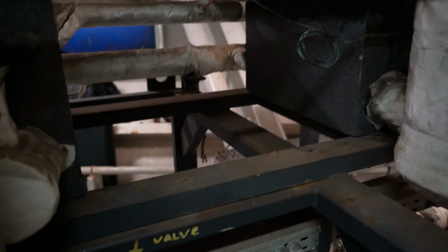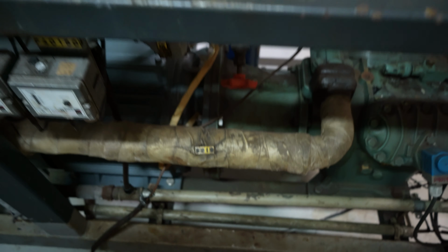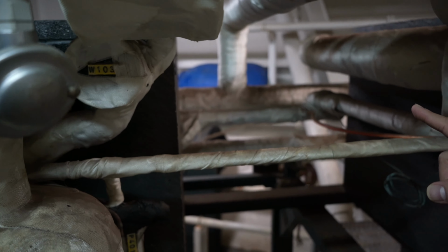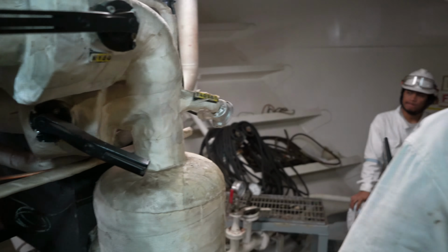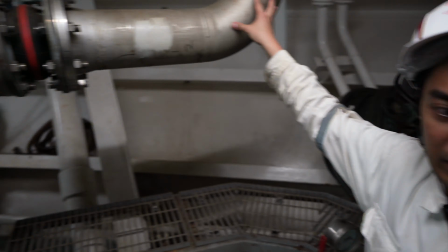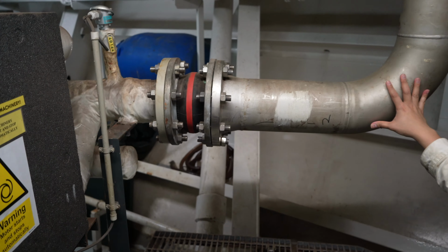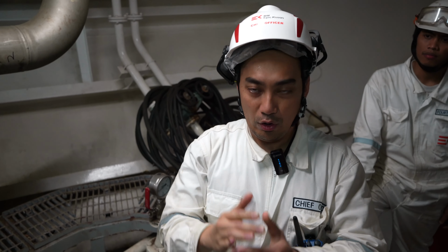In the evaporators, the refrigerant is also passing by for the exchange, in order to take out excessive moisture within the air before it is driven outside. And when it's driven out, this will be the line of it. We make sure as much as possible to have a dew point of 3 degrees or lesser.